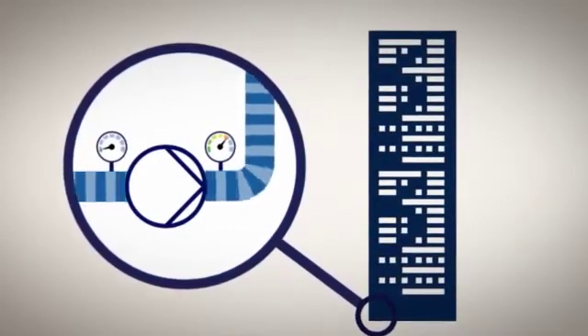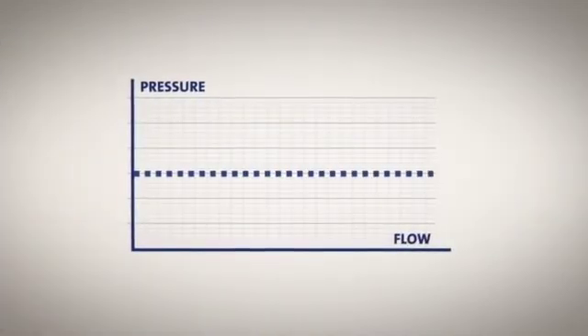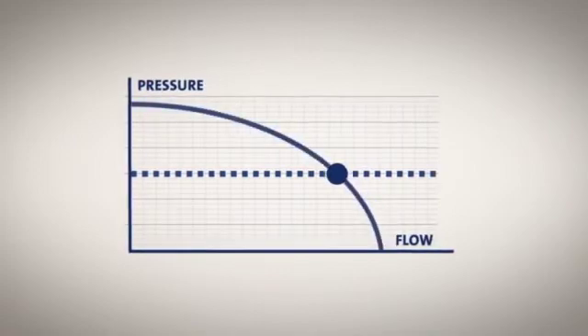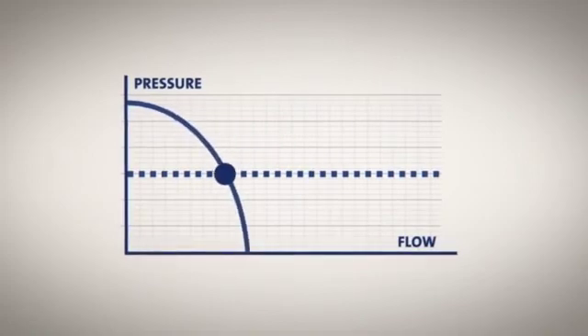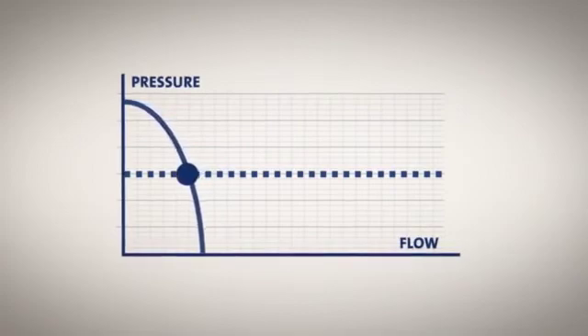So, how do you make the booster set do that? Well, once you have calculated the building's load profile, you simply define a pressure set point. The pump will then maintain the same pressure at all times, but will, during periods of reduced water consumption, like during the day or at night, reduce the speed to save energy.